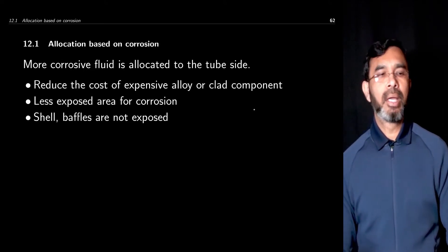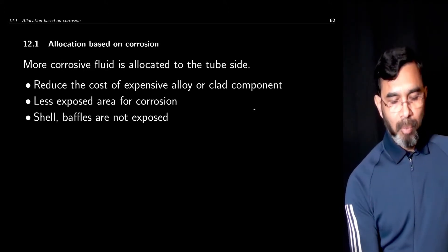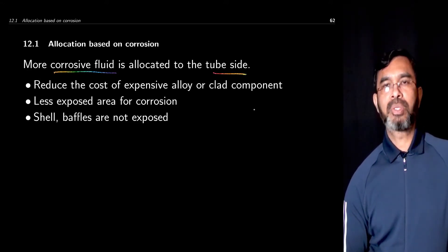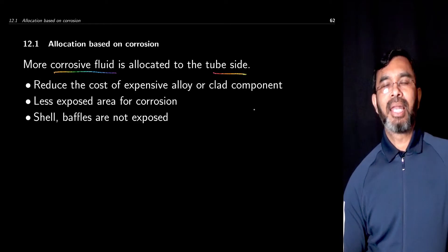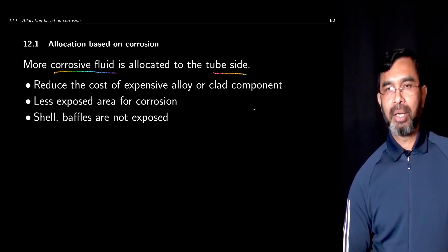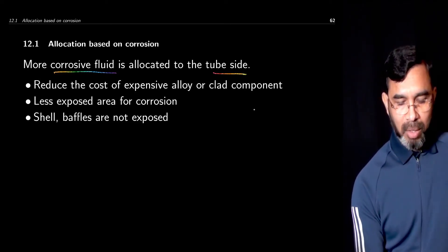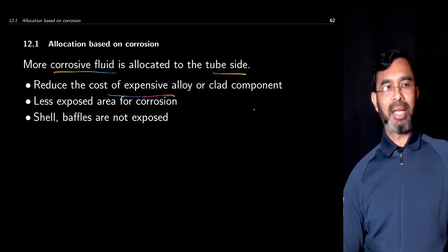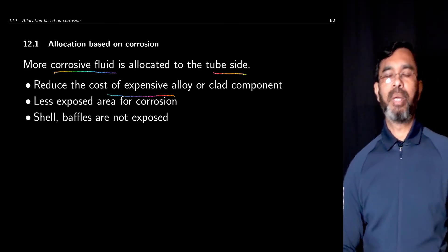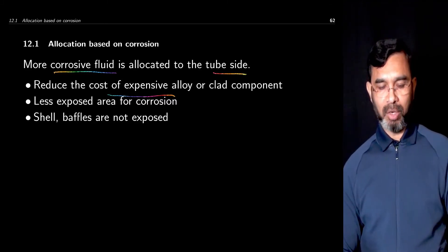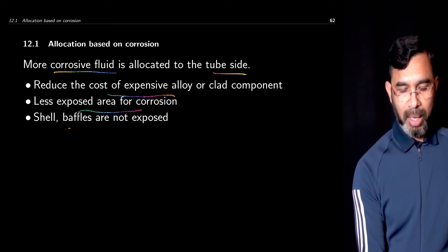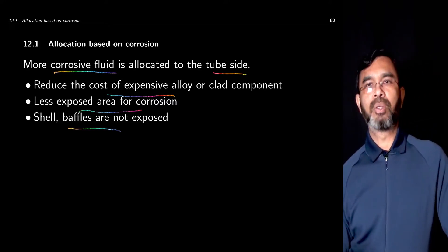When considering corrosion, the more corrosive fluids are typically allocated to the tube side, because on the tube side there is much less area of exposure to the fluid. This reduces the cost of expensive alloys, since if you put the corrosive fluid on the shell side, many different components must be constructed using that special alloy, which will be costly. There is also less exposed area for corrosion, and the shell and baffles are not exposed.